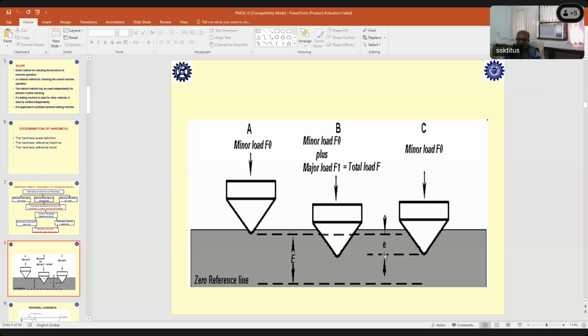Suppose you are making a 100 micron depth. Every 2 micron you have to take as 1 E, so 100 micron will make 50 E basically. Then that 50 you have to subtract from 100 to get the hardness scale. This is how the Rockwell hardness number is obtained as per the standard.